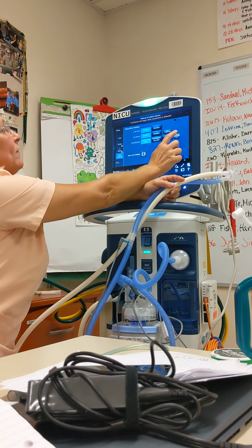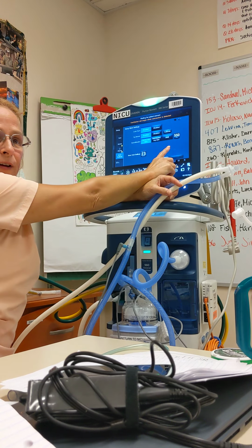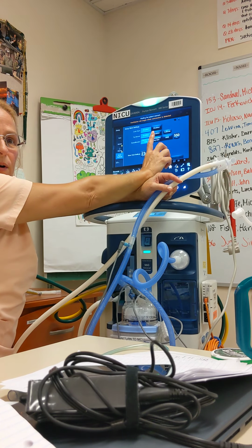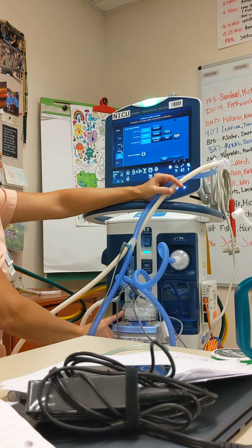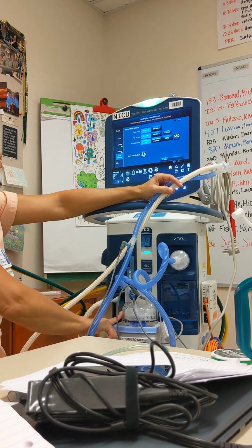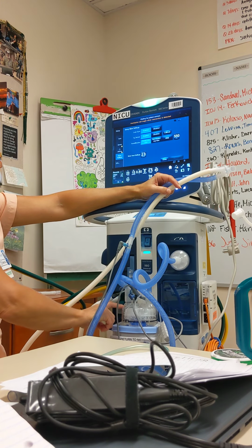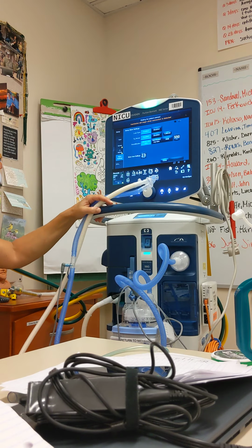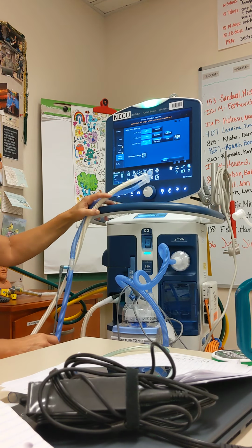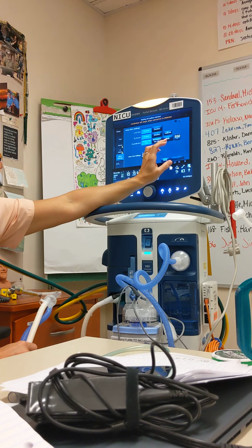Okay. We have to change the volume for the heater to 550. Why? Because it's all based on the size of your chamber. Isn't our chamber the same size? Nope, not the same as the other one, like our adult one, because the circuit's smaller. Okay, I see it now. This is actually bigger than the volume that we put in for adults.